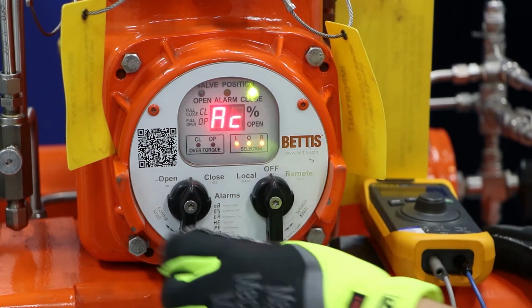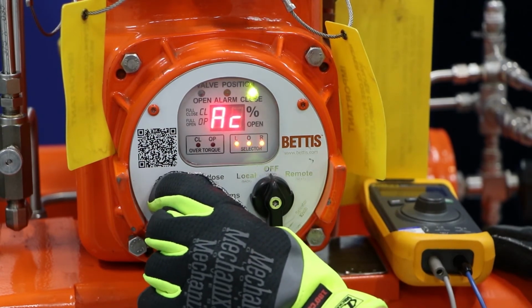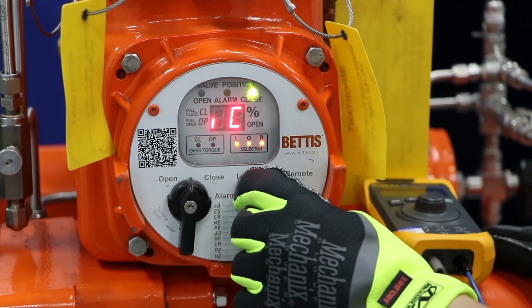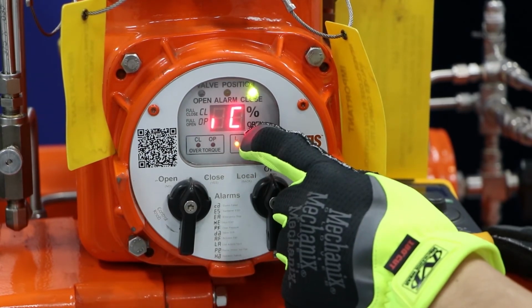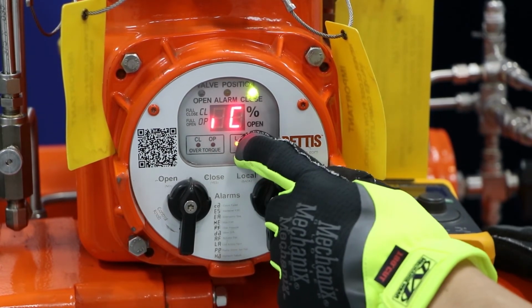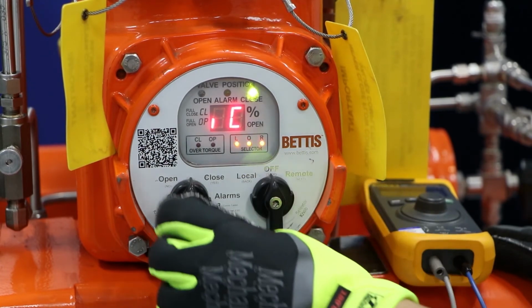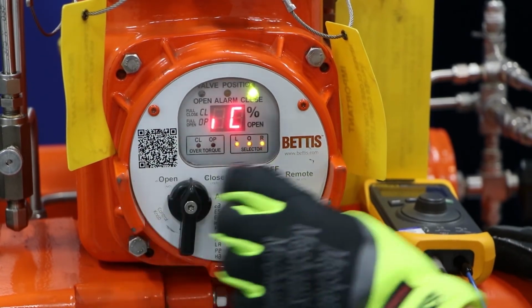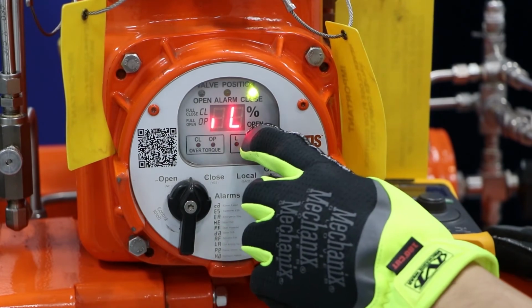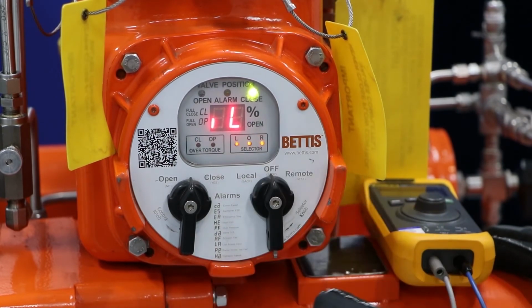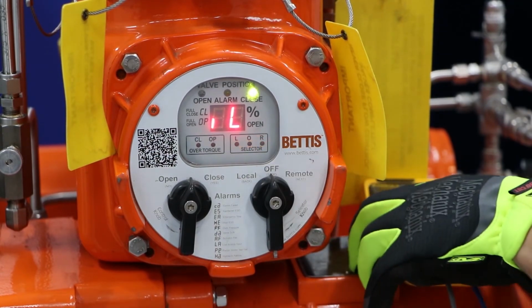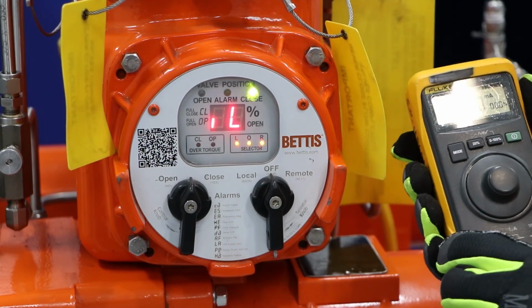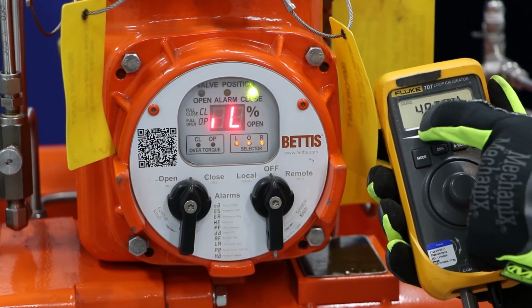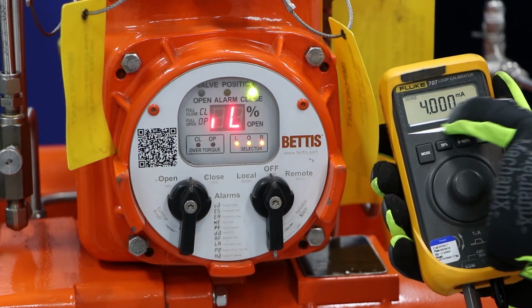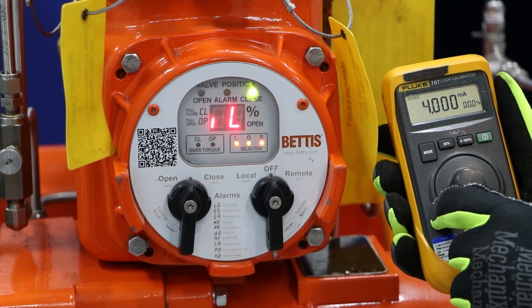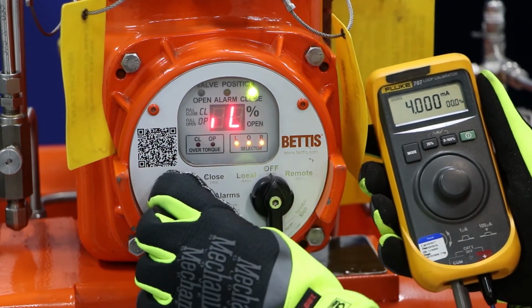When you see AC, toggle yes to enter analog calibration. Next, you'll see IC. IC is input calibration for an analog channel. You want to hit yes again. IL is input lower limit. In order to set your lower limit, go to your current source and make sure you have your lower limit at 4 milliamps. If it reaches 4 milliamps, we're going to hit yes here.